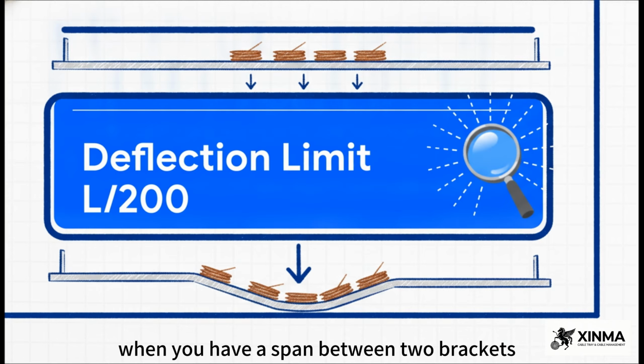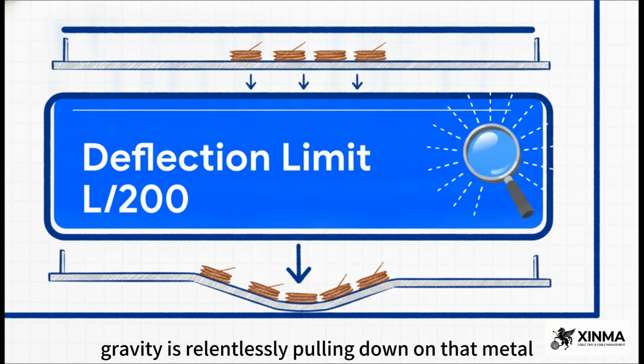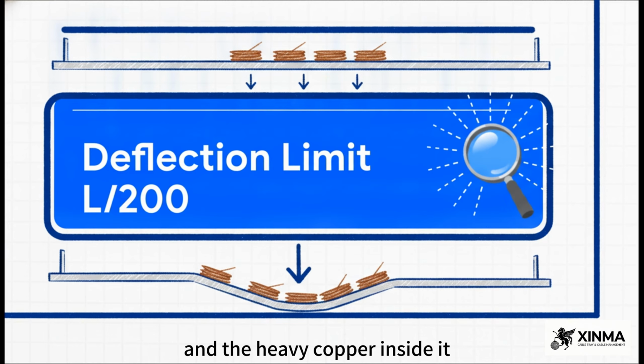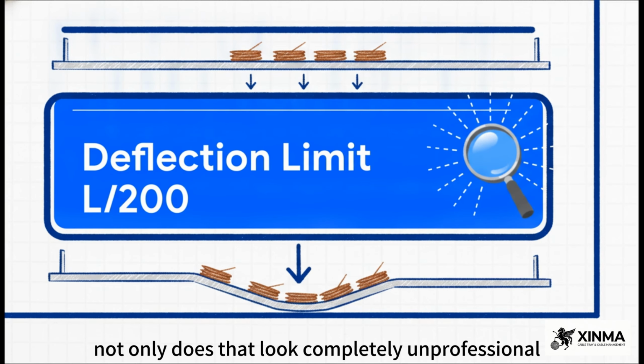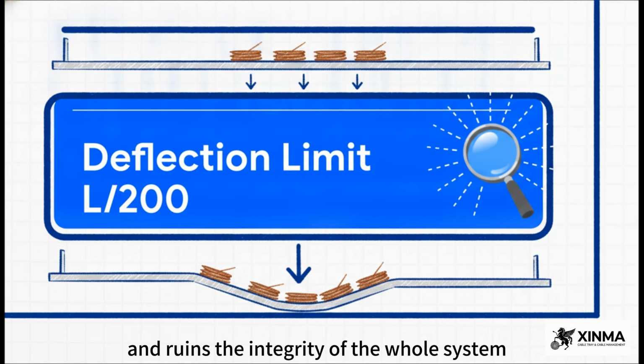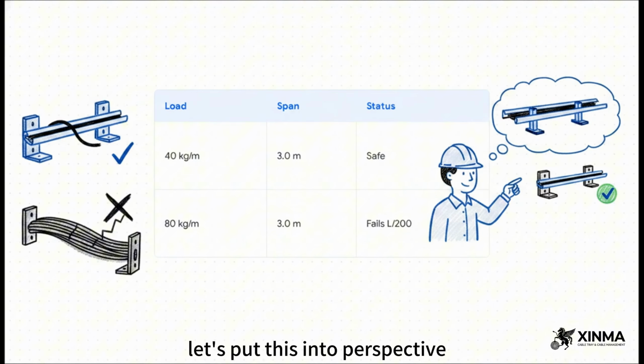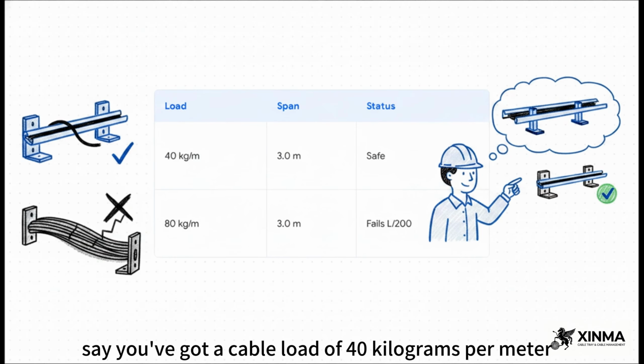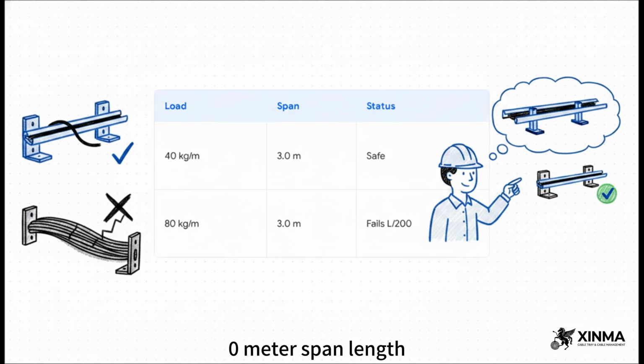When you have a span between two brackets, gravity is relentlessly pulling down on that metal and the heavy copper inside it. Ignore this calculation and you end up with a sagging tray. And look, not only does that look completely unprofessional, but it stresses the cable joints and ruins the integrity of the whole system. Let's put this into perspective. Say you've got a cable load of 40 kilograms per meter and brackets spaced at a 3.0 meter span length. Your deflection status is totally safe.